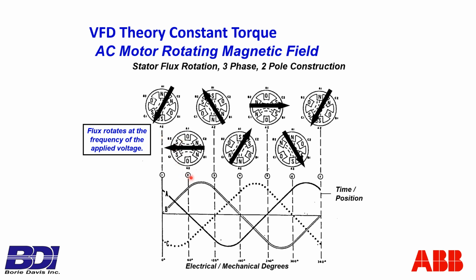Now, if we then look at time 2 here, A is at 0, so that's why these are 0. B is at almost fully positive, and that is B is north here to south here, and C is almost fully opposite negative, so C is represented there. So the field is created from C to B, and that moves that rotor from here over to here. And as we continue, if you looked at every one of these points, it's pulling this motor around in a clockwise direction. Okay, that's the way the magnetic field is rotating in the stator, and it's cutting the lines of force to the rotor, and the rotor's trying to follow it around.